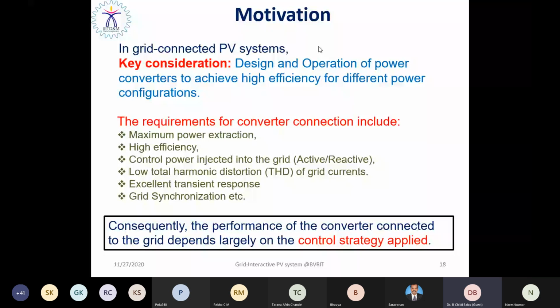The power electronics converter provides an asynchronous interface between the solar PV system and the utility grid to feed power to the grid. Right. So this cannot be directly connected. Then what would be the role of the power converter? As it provides an asynchronous interconnection, it has to meet certain requirements. The grid connection requirements include maximum power extraction. As I told you, energy conversion is not efficient in the solar cell. Its efficiency is not even 20%. So you need to use the power converter to extract the maximum possible power, so that the running cost would be reduced and the efficiency high.